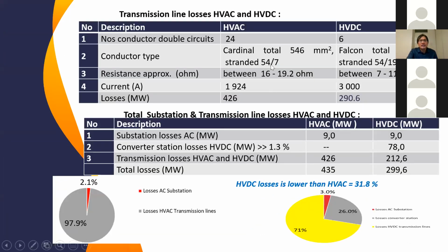And then for the losses, by making assumptions, these are the transmission losses. For AC we have 426 megawatt, and for HVDC we only have 290.6 megawatt. For substation losses, we assume the same because we are using the same AC substation. This is the losses of power converter in the AC substation. Converter losses here, we assume 1.3%. This is quite big, but this is only an assumption. So in total, we have 78 megawatt.